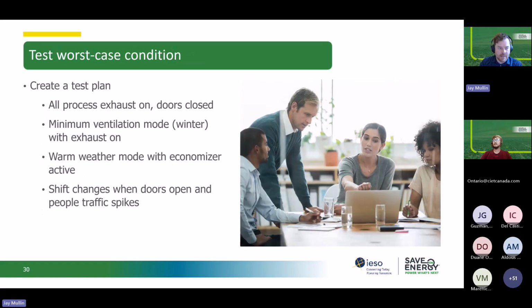Once you've identified these, one thing that's really important to do is to test the worst case condition. As I mentioned, you want to start collecting data under different operating conditions, but in doing so, it's really good to think about what those worst case conditions are, where either your exhaust is really high and supply is really low, or vice versa. Your supply is really high, your exhaust is really low, and test for those. So this could be things like, all the processes are on and all the bay doors and exterior doors are closed. So there's not a lot of air coming in, but there's a lot of air going out.